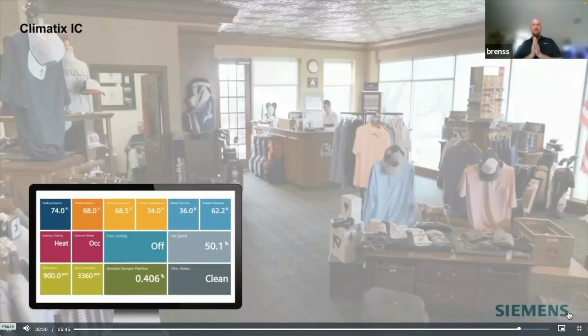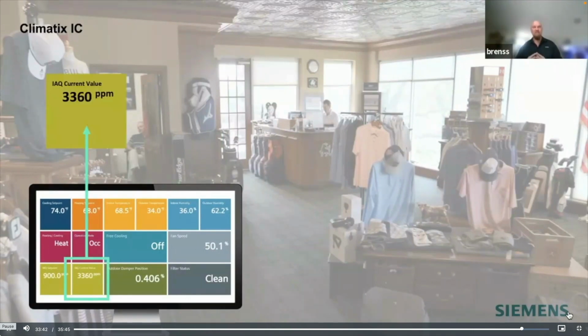Let me tell you a quick story about one of the country clubs that we've installed a unit in. As you can see here, we've installed this unit and we turned it on and we looked at their dashboard and we noticed that there was almost 3,400 parts per million on the indoor air quality. Anybody that knows indoor air quality, that's a little bit out of range. I would say quite high. We generally look for under 1,000. Our set point's 900, but it could be changed.